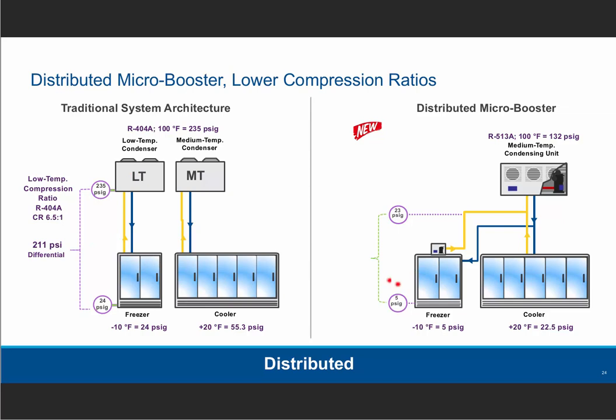The one on the right never changes because my suction in the micro booster is 5 pounds for 513A at minus 10, and I'm discharging into a plus 23 suction. So that differential is only 18 pounds of lift, and the compression ratio is only 1.9. So regardless if it's 110 degrees outside or minus 20, this lift will always be the same. The heat of compression will always be the same.